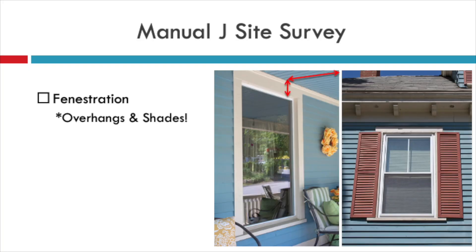For overhangs, you want to measure the height above the window to the overhang and then how far in feet the overhang hangs over that window. If it's not a two-to-one ratio or more, it's not going to provide shading. As you can see in this picture, there's a huge porch on the front side of my house — way more than a two-to-one ratio. Juxtapose that with my daughter's bedroom taken at noon: that little bit of soffit hanging over is not providing shading. It does not have a two-to-one or more ratio, so we don't include it in the load calculation.